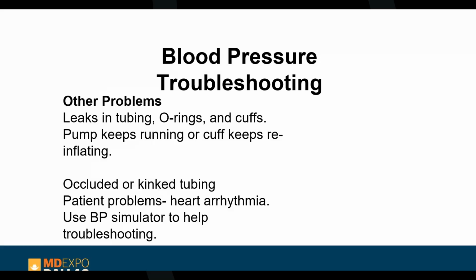Blood pressure troubleshooting, other problems: leaks in the tubing, leaks in the O-rings or the cuffs, any of those can leak. What happens when that leaks is that the pump just keeps pumping and inflating and won't stop, and usually you'll get an error. I was just working on a V100 and I want to say it was error E83 maybe, I don't remember, but some error popped up, and I looked it up in the book, and it has a leak somewhere. Where I work, we use Medline cuffs, which you'll see a picture of in just a minute. So we have an adapter that adapts the two into one, because the Medline cuff has one connector.